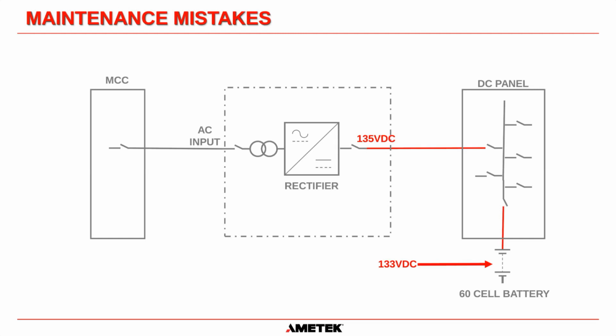Also, if the battery room is in a different location, you have this cable here going to the DC panel, and then you have this cable here coming from the DC panel to the battery. That could be 200 feet. Could be more, it could be longer. So there could be some volt drop in that cable. So you could measure 135 volts DC at the charger, but if you go out to the battery, because of the volt drop in the cable, now it'd be unusual for it to be too much of a volt drop because there's a very small amount of current flowing through it, but it could go down to 133 volts. And that means if the manufacturer says that it has to be charged at 135 volts, that battery would be undercharged.